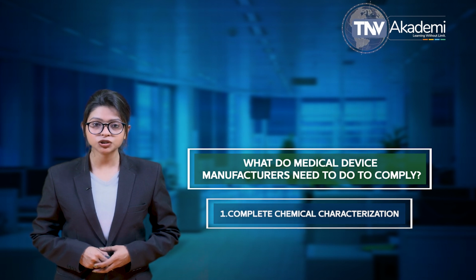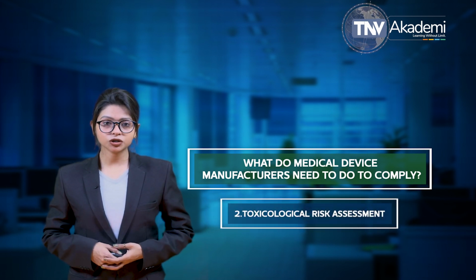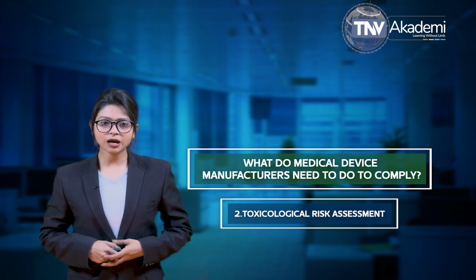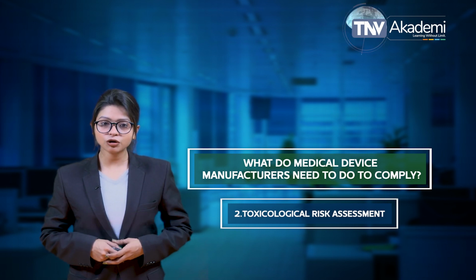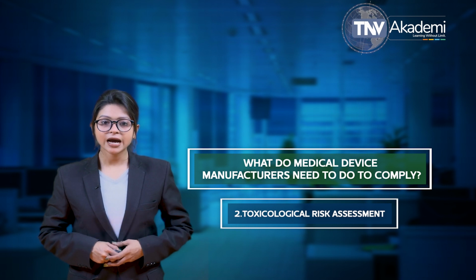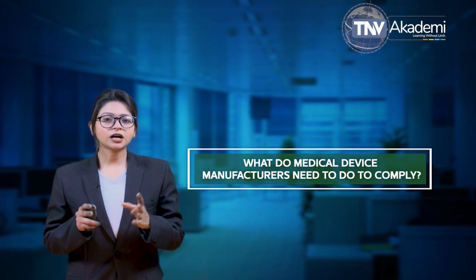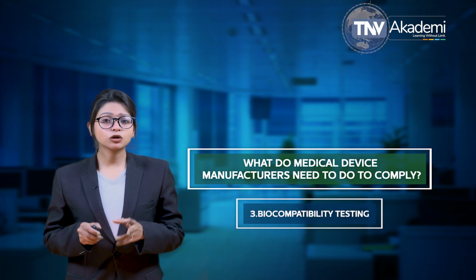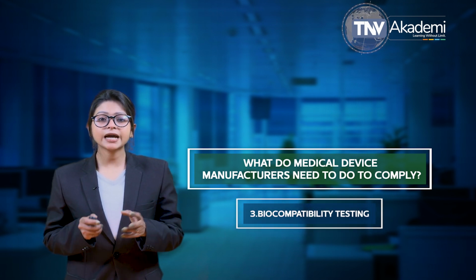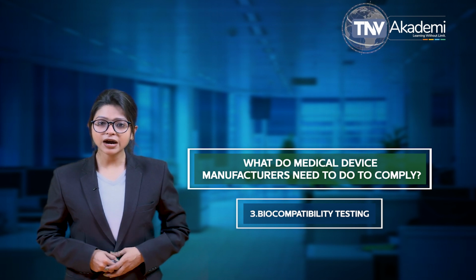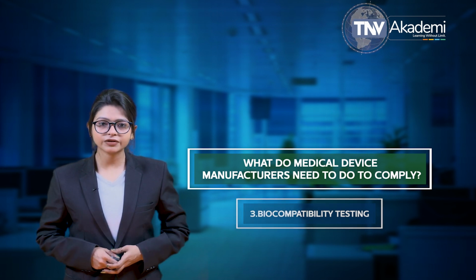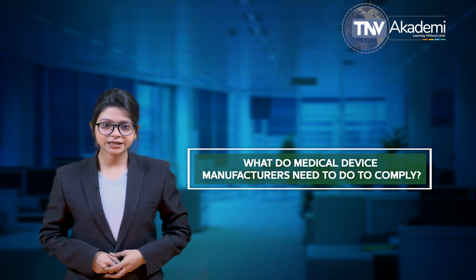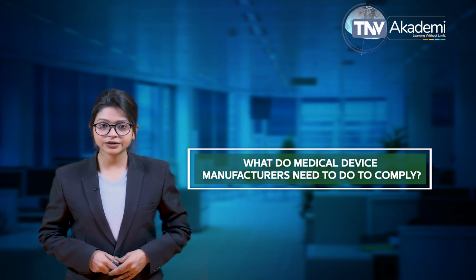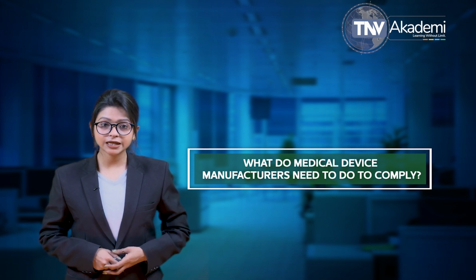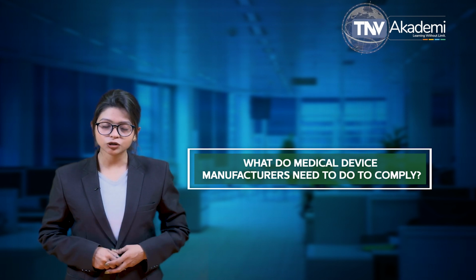The second one is toxicological risk assessment. It considers each chemical and its quantity and derives a margin of safety based on patient population and intended use. The third one is biocompatibility testing. It covers local effects, for example irritation, and any systemic effects specific to the device that could not be addressed in the toxicological risk assessment, for example pyrogenicity. Testing may also need to be conducted to mitigate potential concerns identified in the toxicological risk assessment, for example genotoxicity or subacute and subchronic toxicity.